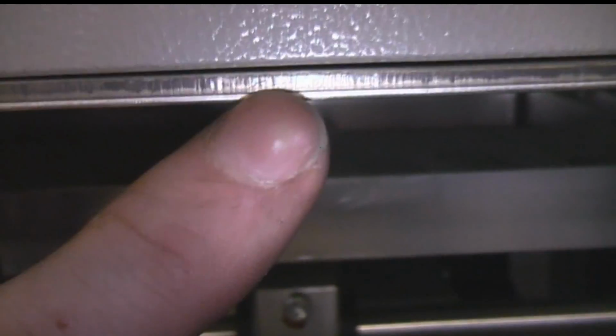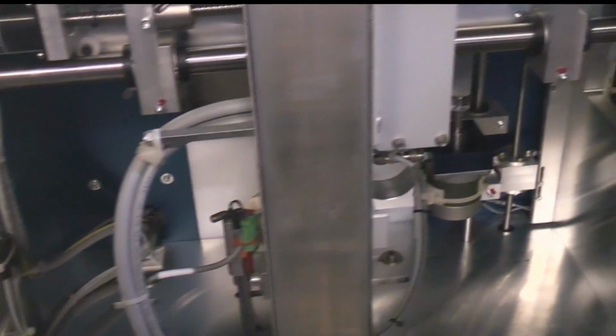A slightly interesting thing is this base is actually made out of about 3mm brass sheet. I'm not quite sure what's so special about brass, unless it's maybe to do with X-ray shielding. The doors and the lid, they've actually got a sandwich of an aluminium sheet and then a chunk of lead. That's about 4mm thick lead sheet. And they've got that in the side doors, and also basically everything up to about here. So you can see it's partly across here and then partly on the back panel.